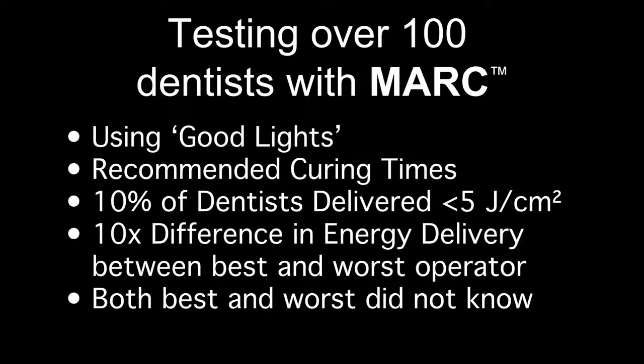We have tested over 100 dentists using MARC. Using good curing lights for recommended curing times, 10% of dentists delivered less than 5 joules per centimeter squared. And none of those dentists knew how little energy they were delivering.